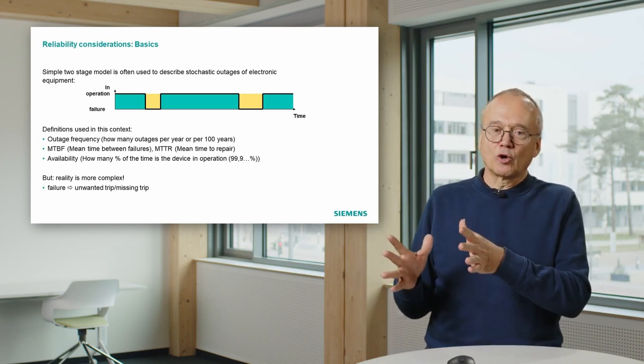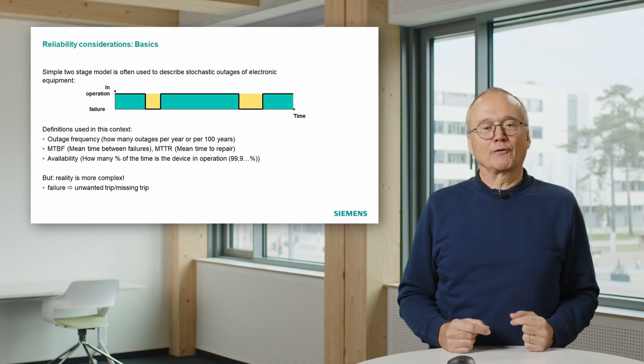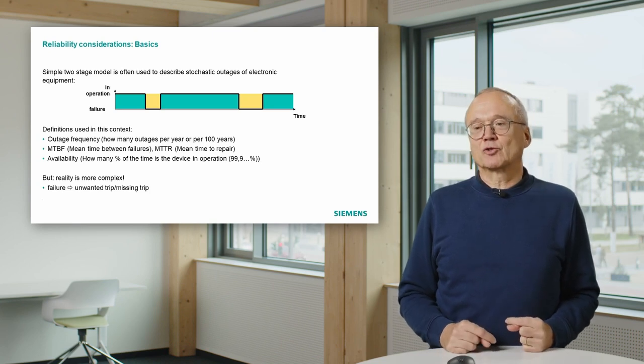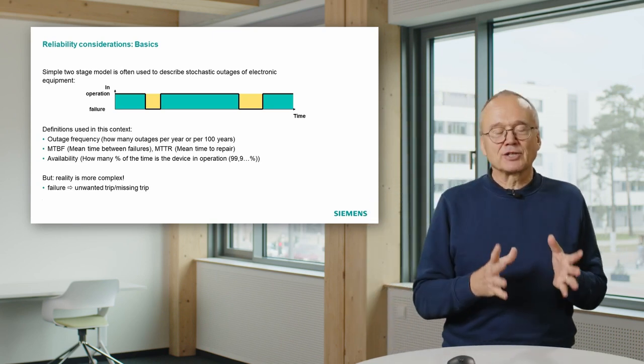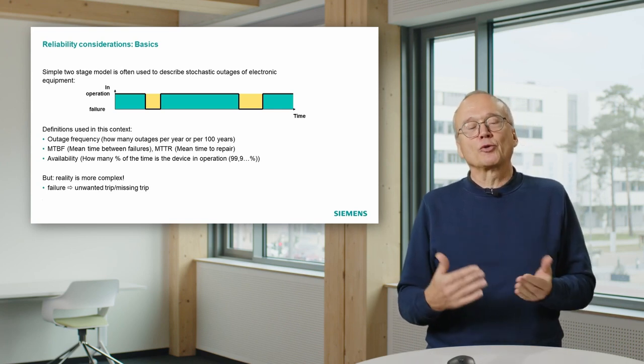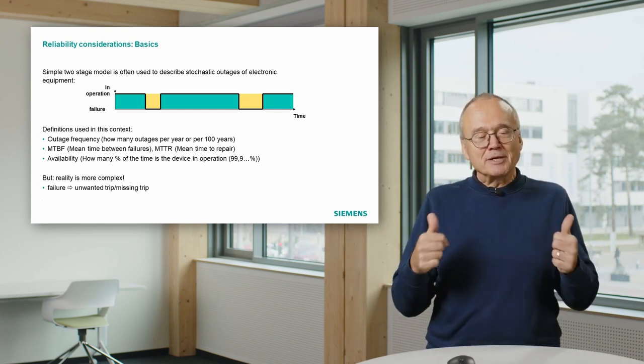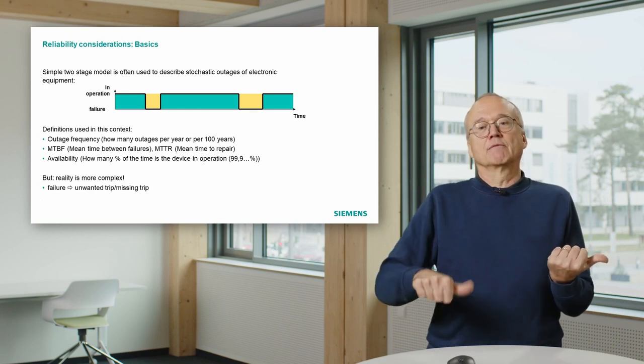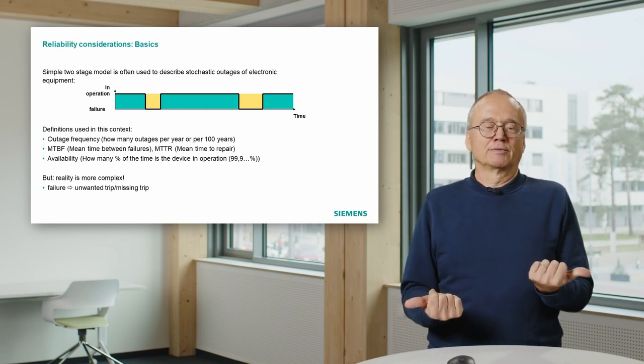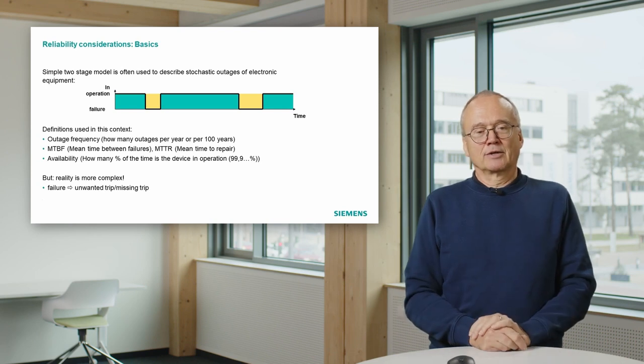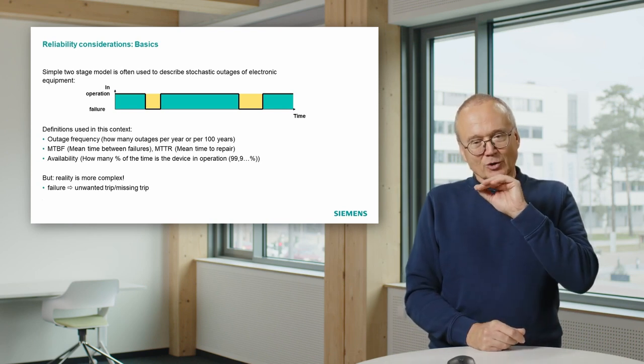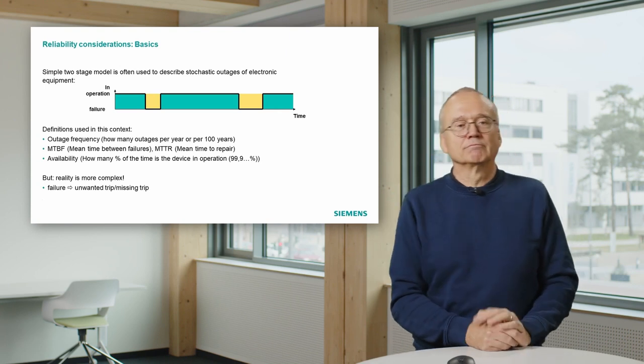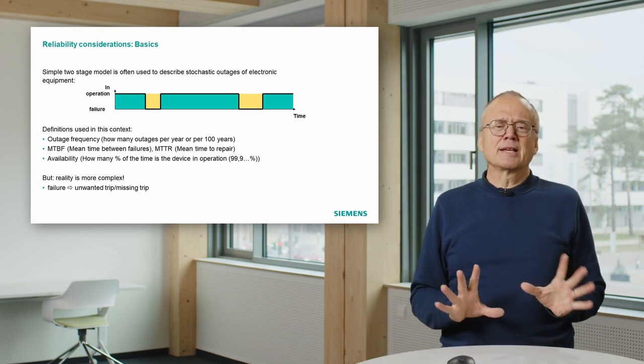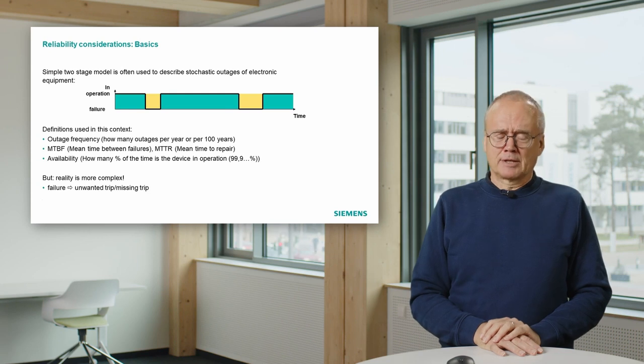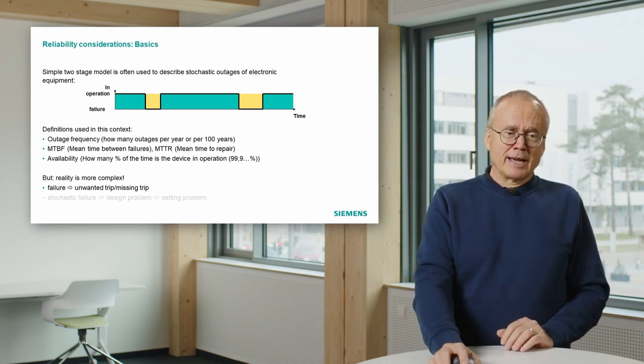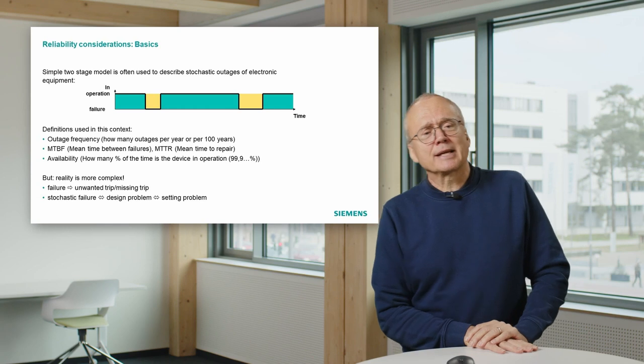That type of failure is called missing trip, but we have another type of failure, and that is called unwanted trip. Theoretically, it's possible that a protection relay gives a trip command although there is no fault. That means we can fail in two different directions, missing trip or unwanted trip. Both are things we don't like. So that means already that this simple two-stage diagram of operation and failure is a simplification which doesn't really fit to protection. And there is another thing which has to be taken into account.